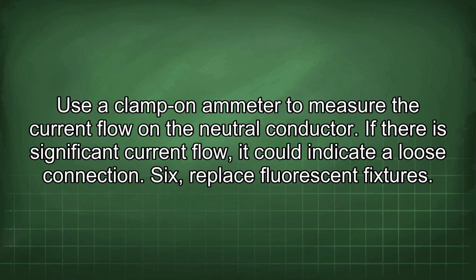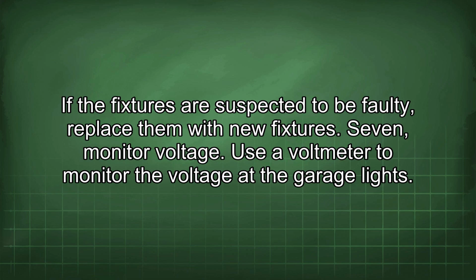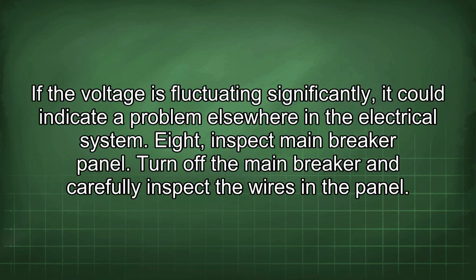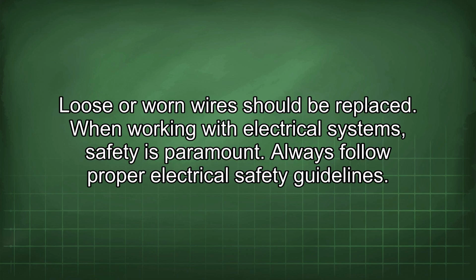6. Replace fluorescent fixtures. If the fixtures are suspected to be faulty, replace them with new fixtures. 7. Monitor voltage. Use a voltmeter to monitor the voltage of the garage lights. If the voltage is fluctuating significantly, it could indicate a problem elsewhere in the electrical system. 8. Inspect main breaker panel. Turn off the main breaker and carefully inspect the wires in the panel. Loose or worn wires should be replaced.